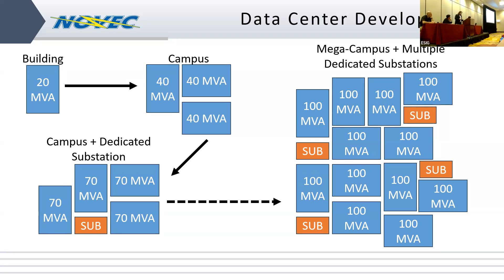When you build a new data center, you don't put everything in there, wire it up, set up the HVAC, and then come to the utility and say turn on my lights. They turn on the lights as soon as possible, so you've got servers running in room A while you're building out room B, and over time the building's load ramps up.